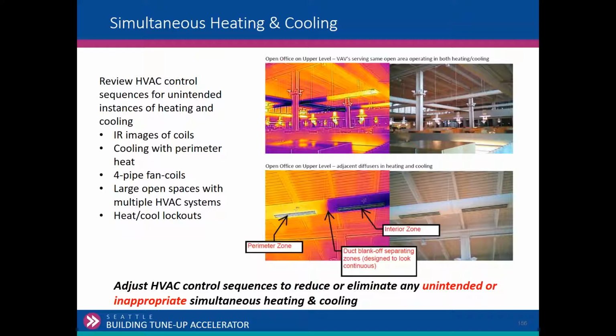Yeah, so the reason I'm curious is that generally people want to have the same temperature throughout their space. They don't like going from hot spaces to cold spaces or that type of thing. So I'm just curious, that's in the code language now, because we were looking at VAV buildings for energy performance, and they weren't performing very well. All that South Lake Union, Amazon, VAV stuff is not our better performing buildings. And this is one of the things, in fact, if anybody is knowledgeable of the code, there's now a high efficiency VAV option because we were trying to address the inefficiency of VAV. No, I doubt that. It was a slow response. Yeah, no, we're just trying to figure out if we can make VAV more efficient. We'll know more in the next code cycle.